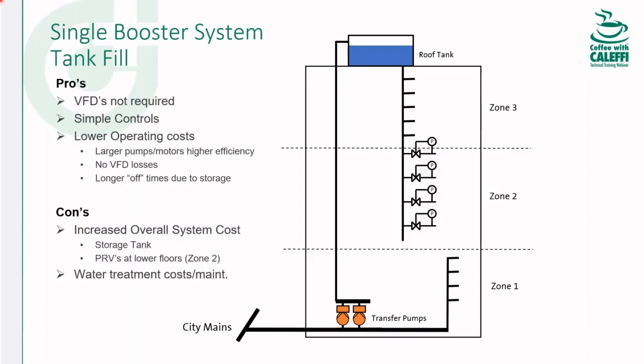So Reece, any pros and cons you wanna call out on this one? Sure. So again, like Adam said, your pumps just need to be sized to move the water up to the tank. So they don't need drives. They can be fixed speed. You can select them based on best efficiency, and you can use large pumps so that when they are in tank fill mode, they're running at a good efficiency point on the curve. The controls are simple: low water, turn the pump on, high water, turn the pump off. So you're just going off a level in the tank.